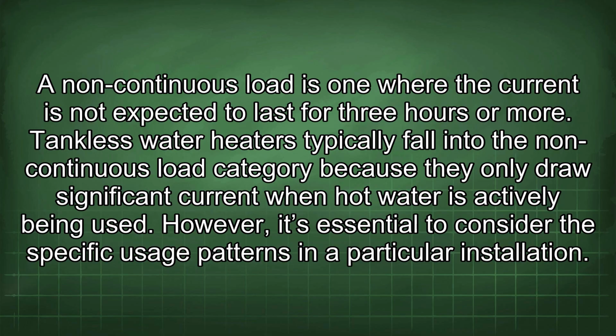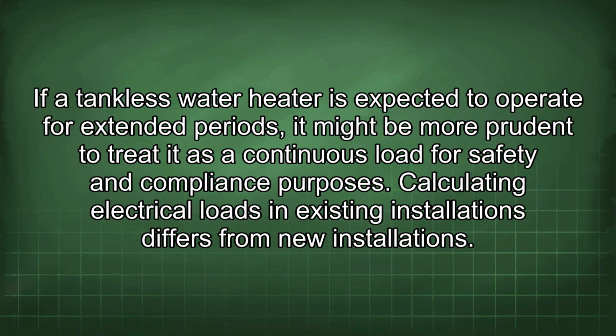Tankless water heaters typically fall into the non-continuous load category because they only draw significant current when hot water is actively being used. However, it's essential to consider the specific usage patterns in a particular installation. If a tankless water heater is expected to operate for extended periods, it might be more prudent to treat it as a continuous load for safety and compliance purposes.